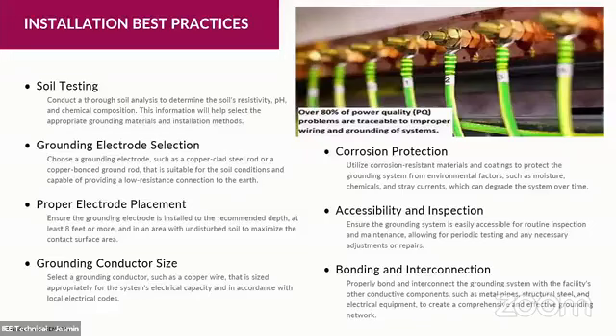We consider it as the directly buried type with a 2 feet depth, with specific connection to our system. We have the proper electrode placement as discussed, the three methodologies: driven to the ground 8 feet below, from the tip up to the top exposure to the ground, the 45 degrees method, and lastly the directly buried or in a concrete encasement of a 2 feet depth.